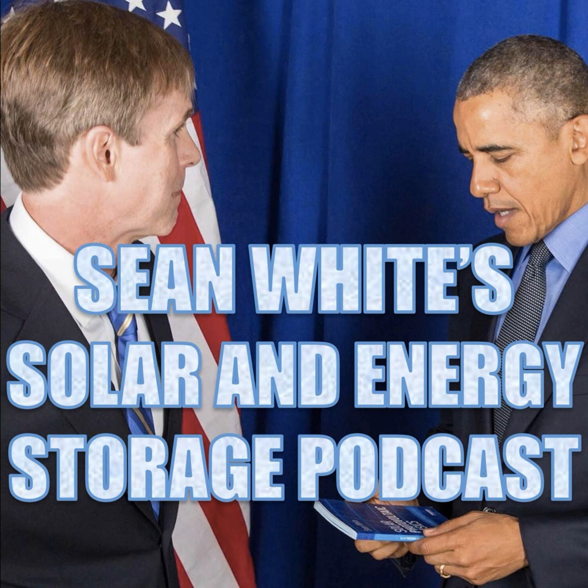The standalone source determines the size of the conductor, obviously. So it's like however much your inverter can put out, for instance, would be how big your conductors would be. And then if you had more than an inverter, size it based on your inverter plus your generator sometimes, perhaps. Let's say you have a 100 amp panel board, but your inverter can only put out 50 amps, then you don't have to size your conductors based on 100 amps. Correct. Yeah, it's based on the power source size, not on the load center size.